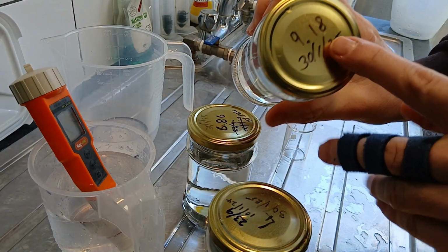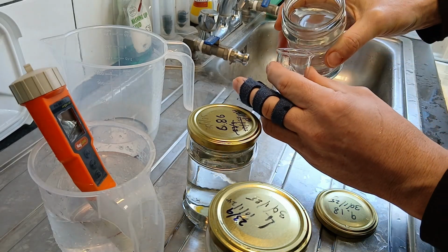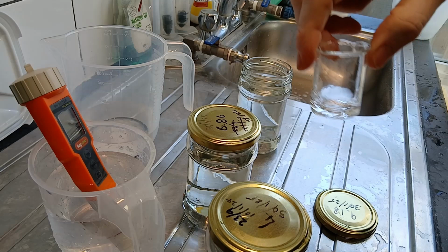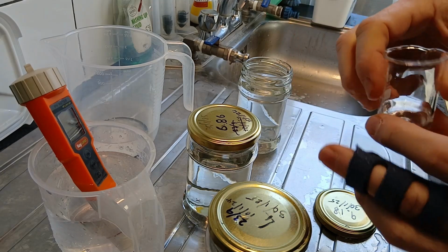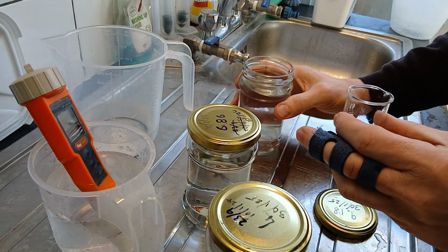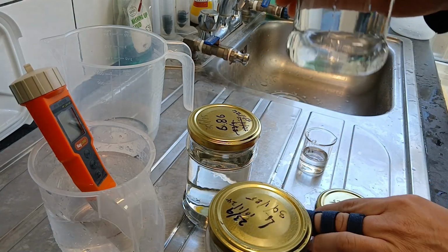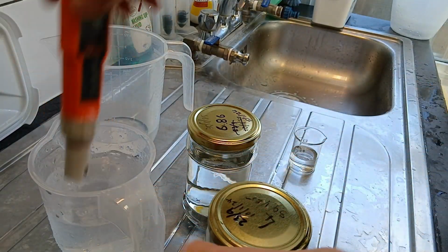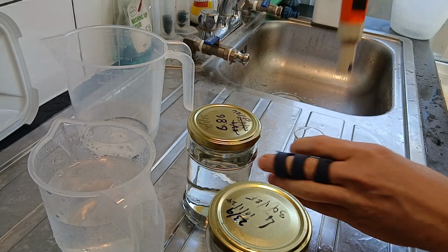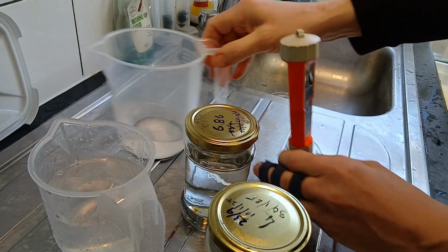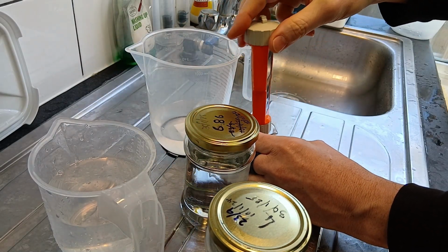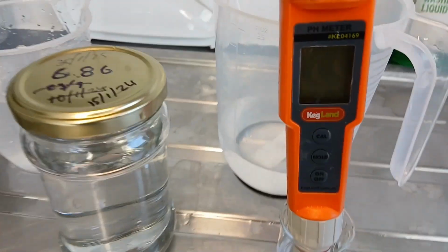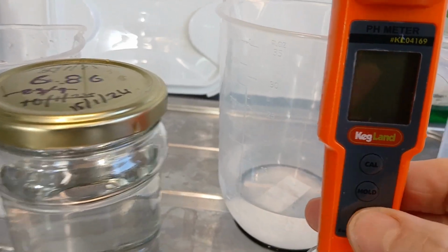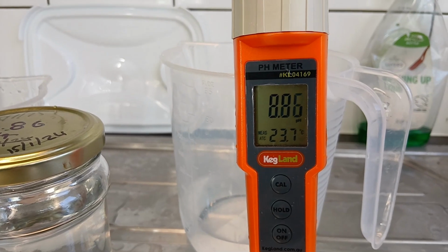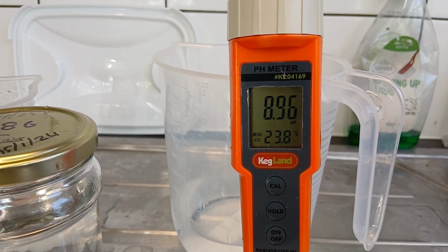Now we're on 9.18. Again, just a little bit of the solution in the bottom there. Just swizzle that around, just to coat the surfaces and try and remove any of that residual other buffer or water out of there. Again, about 15 ml in there. As you can see, we've got 250 ml of this, so we should have plenty for more calibrations. pH meter out of the water, shake it dry as best we can, get it into the solution. Let it sit there for a minute. Okay, so pH meter on, now it's in solution. So we're looking for 9.18, steadily rising up.